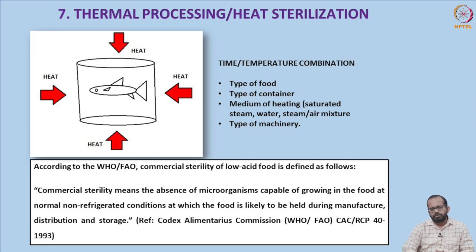The heating medium that we use is steam. The transfer of heat is by condensing. The phase change is there. It has a good latent heat capacity. By condensing, what happens is it generates more sensible heat. Hot water is around 500 watts per meter squared degree Celsius. That may be the heat transfer coefficient of hot water. But in the case of steam, it is around 10,000 watts per meter squared degree Celsius. So that much difference is there between hot water and steam. So steam has much more latent heat capacity, and it can transfer heat more successfully than liquid.